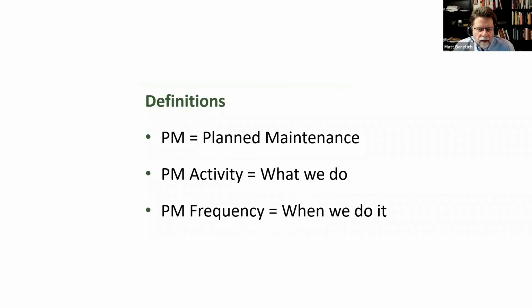When I say PM, I mean planned maintenance. I think you'll see why I tend to shy away from preventive maintenance, because a lot of what we do doesn't prevent anything. But whatever you call it, PM is scheduled maintenance. CMS, Joint Commission and the accrediting organizations divide that into PM activities, meaning what we do, the steps in the PM procedure, and PM frequency, which is when we do it. That could be on a calendar basis, or on runtime hours for a ventilator, or however it's appropriate to decide when we do some kind of PM procedure. Next slide.